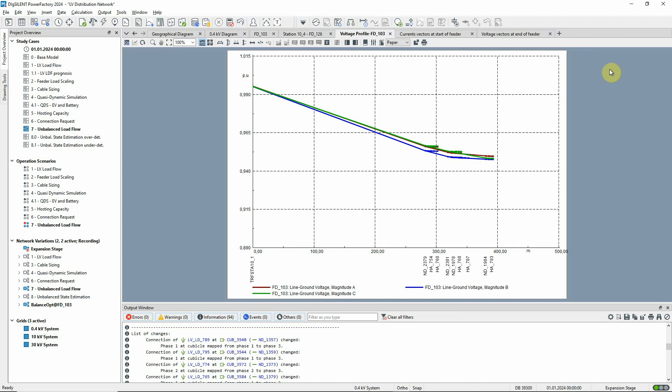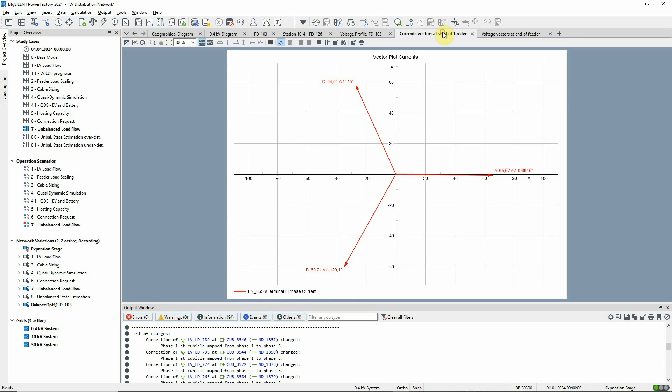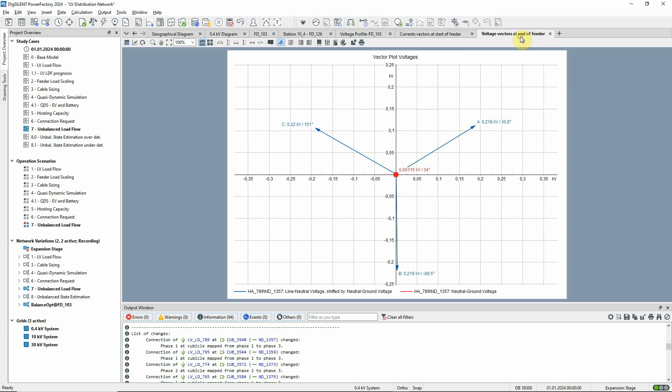Now the voltage profile shows balanced voltages and no lines are overloaded. Looking at the current vector plot, a much more symmetrical system is seen. And in the voltage vector plot, we can see that, as a result of the phase balance, the neutral to earth voltage is reduced too.